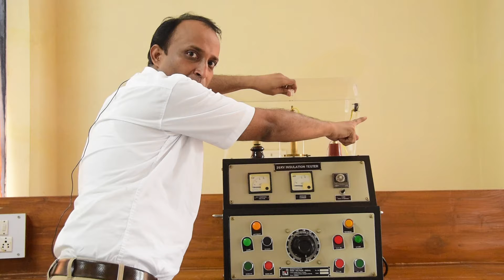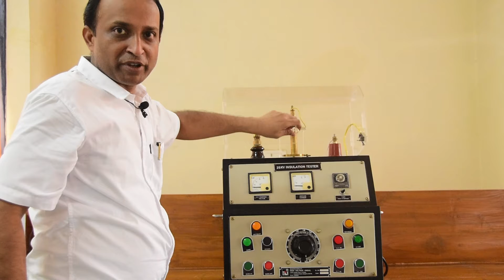Apart from the fiberglass assembly, inside it you can observe at this small notch a limit switch. This limit switch ensures that when we put this cover onto the electrode and close it, the switch gets closed. Only when the switch is closed can the supply be enabled; otherwise we cannot enable the supply. So this is a safety feature. The glass itself is a safety feature, and to ensure that the glass is closed, there is a limit switch on the right hand side of this assembly.